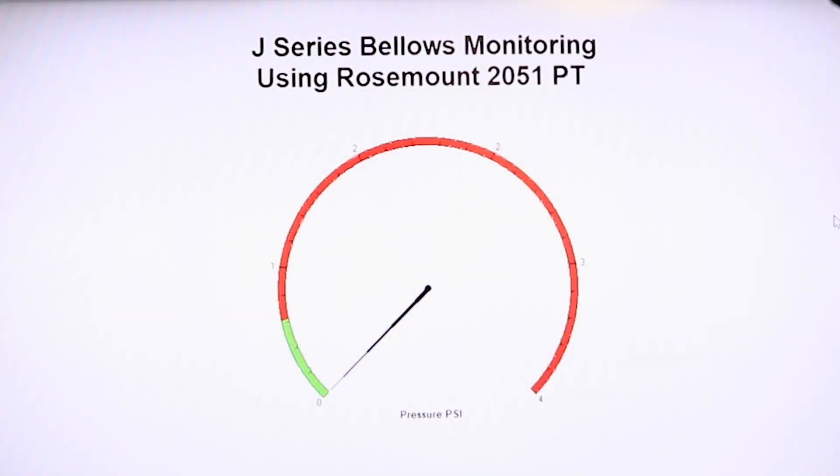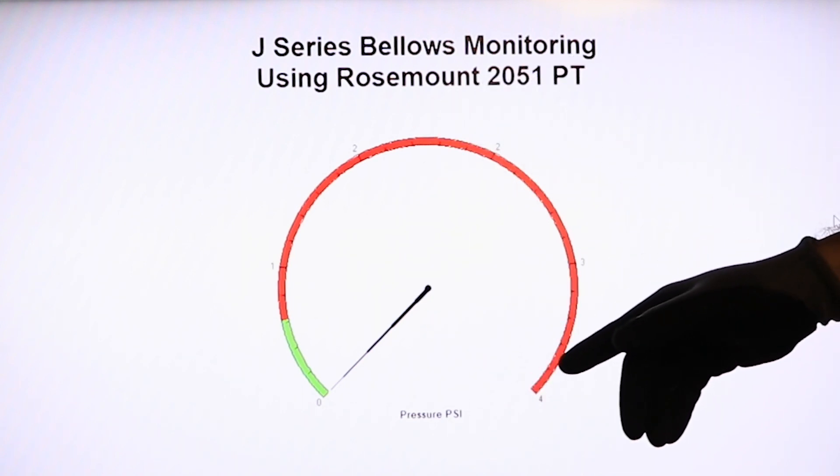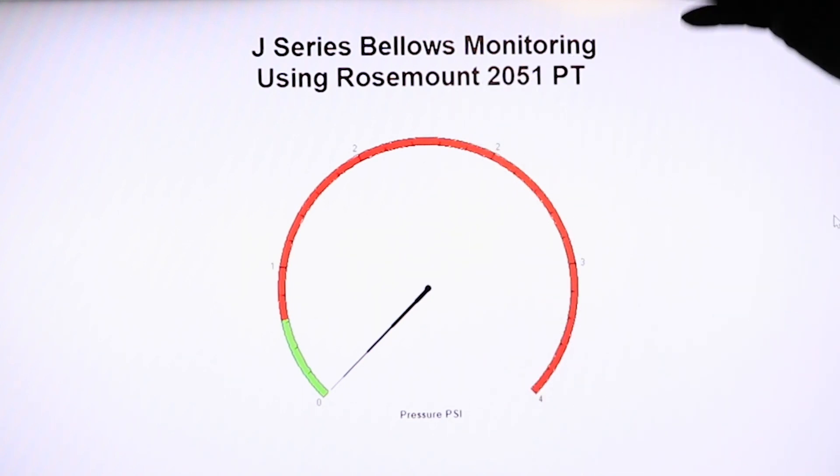In this graph, the only thing we're graphing is the pressure at that secondary chamber that gets created between the bellows and the backup piston. With an undamaged bellows, you should never see any increase in pressure in that secondary chamber. Any increase in pressure that you see in that secondary chamber means that the bellows has been compromised.